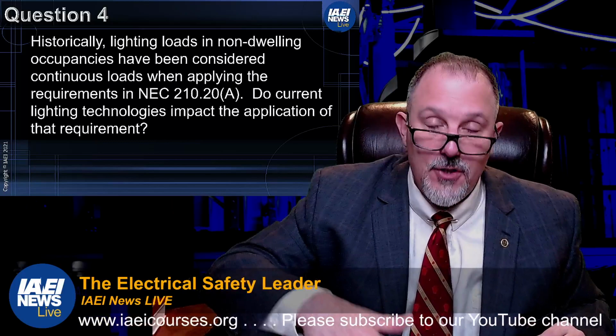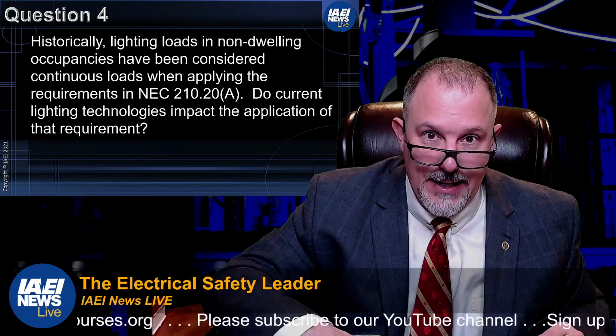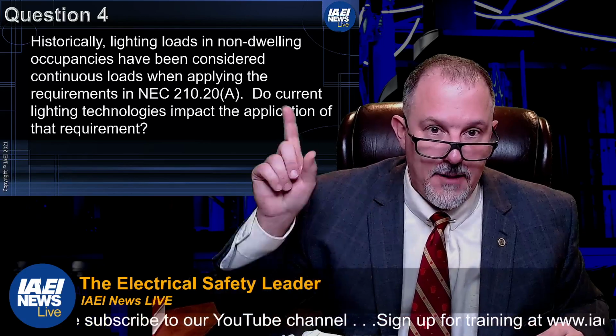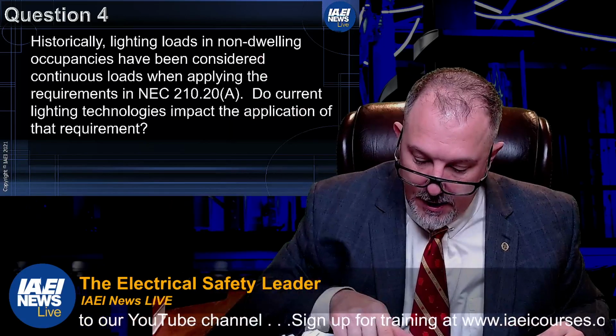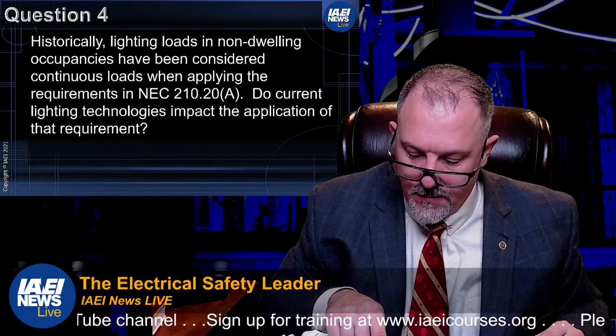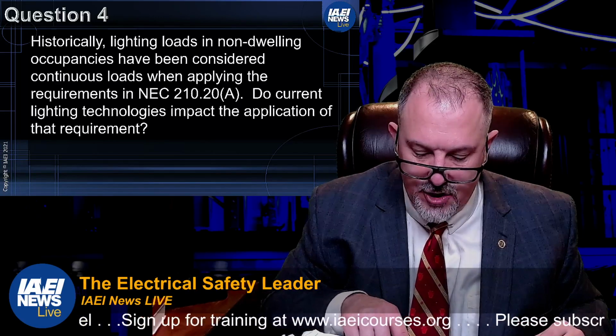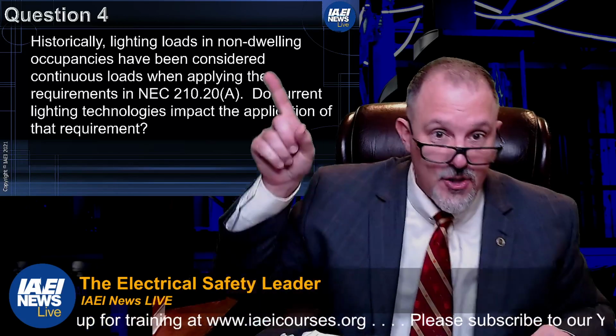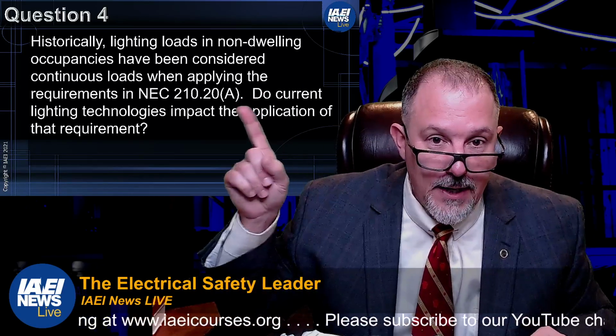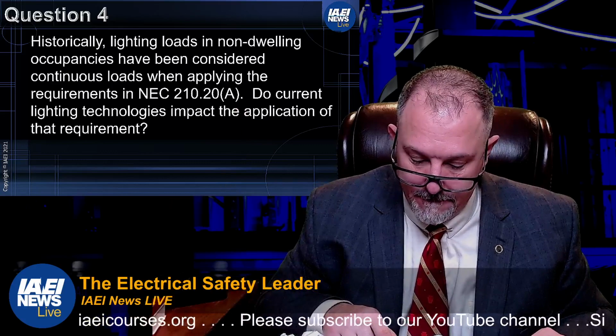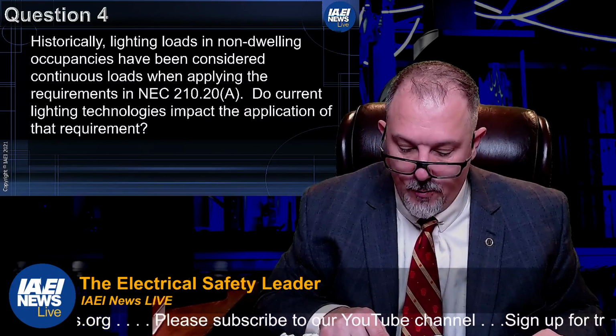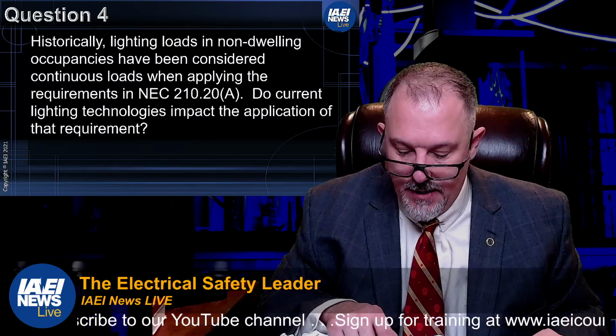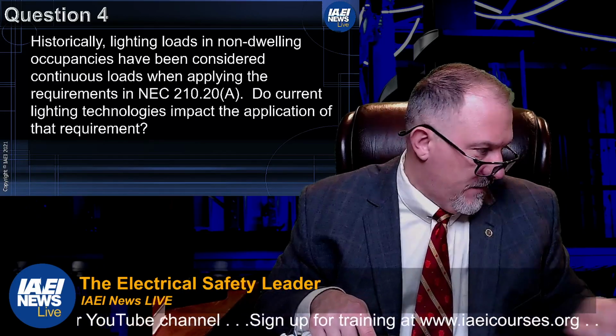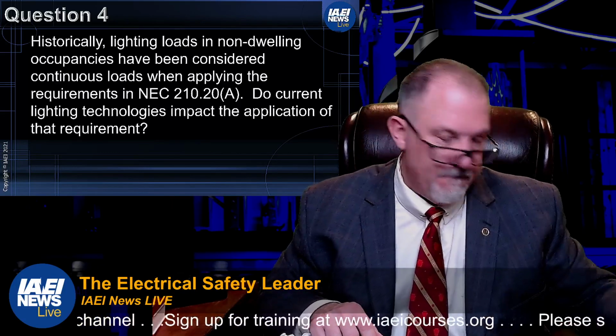Remember, 220.12 is general lighting, okay? General lighting loads, non-dwelling occupancy, right there. And now this says the 125% multiplier for a continuous load as specified in 210.20(A), which is right there. We just read it. I don't even have to go back and read it. Right here, 210.20(A) is included when using the unit loads in this table for calculating the minimum lighting load for a specified occupancy. Okay?